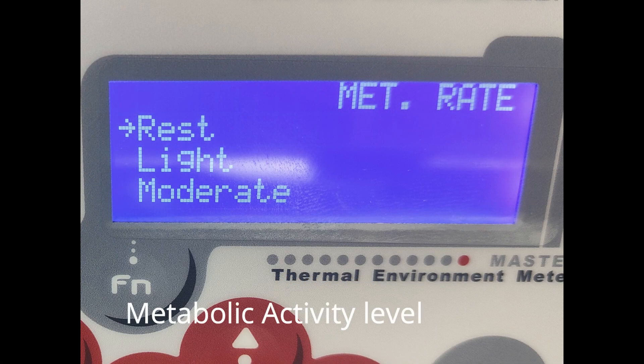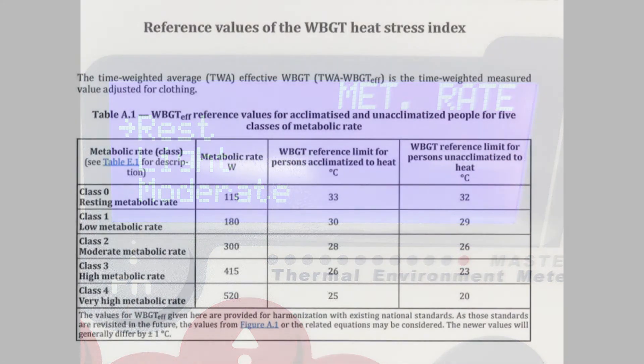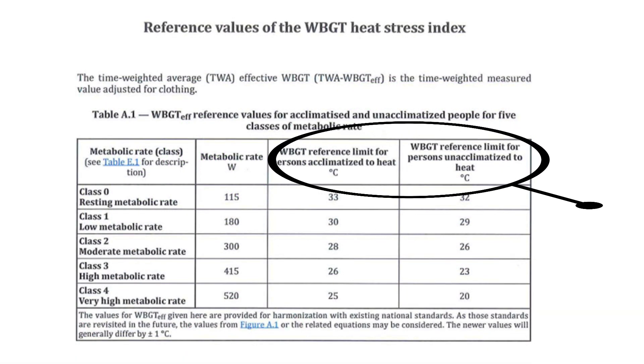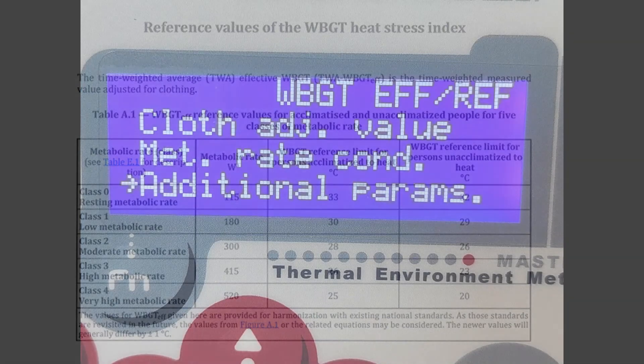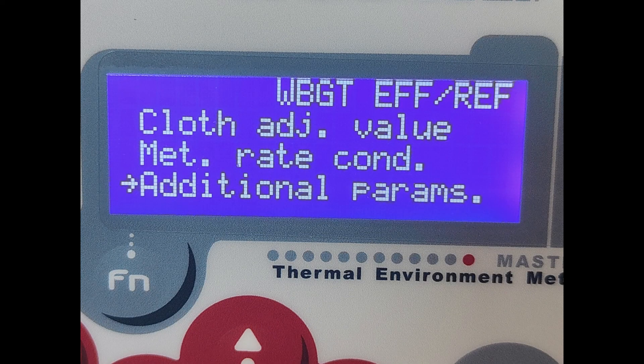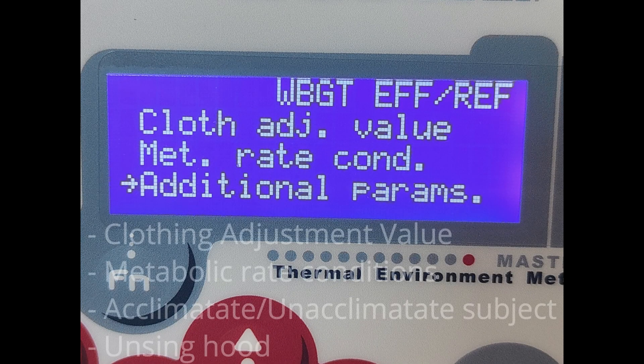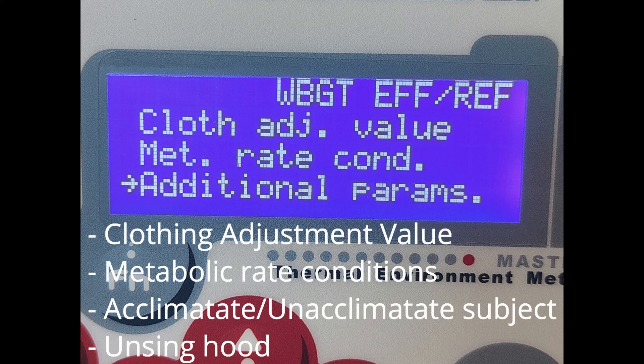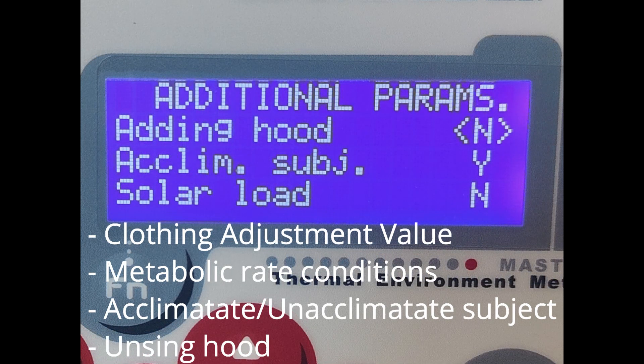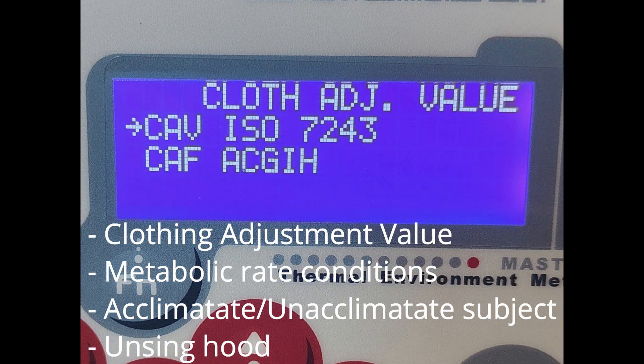Limits are calculated considering the metabolic activity level for each acclimatized and non-acclimatized subject type. All parameters related to the subject — used to produce effective WBGT, WBGT reference, TLV, and action limit — such as clothing, metabolic rate, and acclimatization type, are selectable in the Heat Shield unit by keyboard. Lists are taken from ISO 7243 and ACGIH standards.